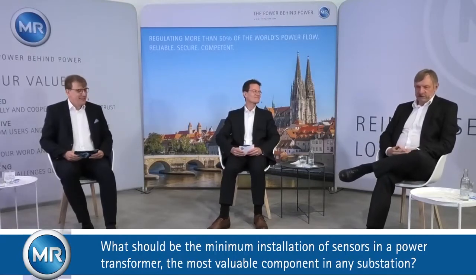We will have a standard fitting of sensors on the standard transformers. You will find temperature measurement, oil level gauges on the transformer, and also a Buchholz relay. That's the standard solution you will find on every transformer, and the big ones also on step-up transformers and phase-shifting transformers.